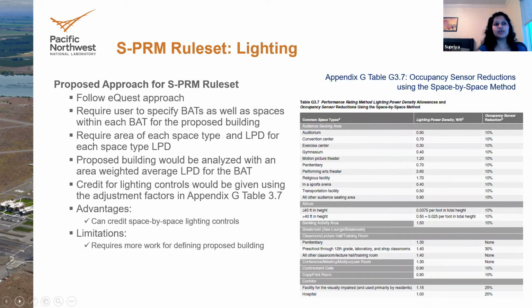This also allows us to use the lighting control reductions, which are specified in Appendix G, at a space type level. So this way we could maintain that level of distinction where controls are applied at the space level, and we could also use the reductions which are specified in Appendix G. So there can be credit for lighting controls at the space type, but the limitation of this approach is that a user, the modeler or the architect, would still need to go through the process of defining the space type composition for each building area type.